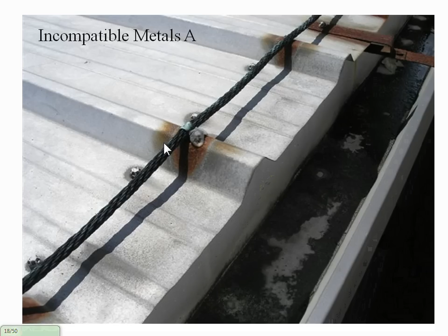I have a couple of pictures. This was somebody who mounted the copper cable. It's a little hard to see on an aluminum roof. You can see how they're starting to corrode around here. And this was only after a couple years. If you were to leave this copper cable on this aluminum roof for, let's say, another 10, 15 years, it'll actually eat a hole directly through the roof. So when it comes to picking materials, it's very important. Copper's mounted to copper, aluminum's mounted to aluminum. Otherwise, you can see what happens.